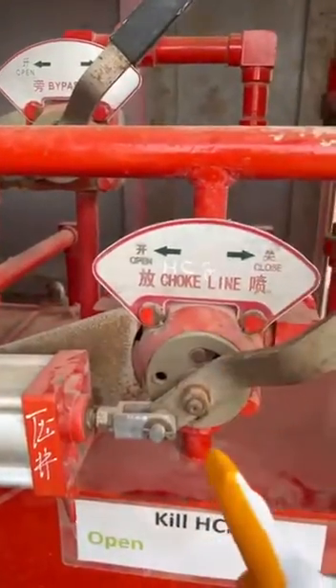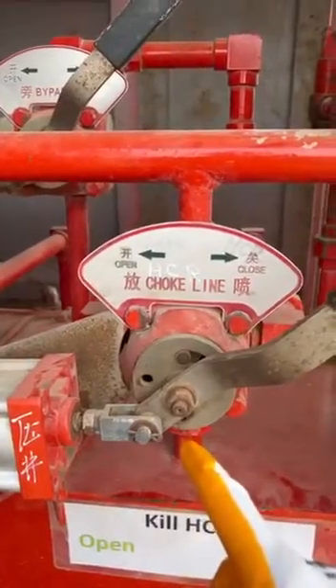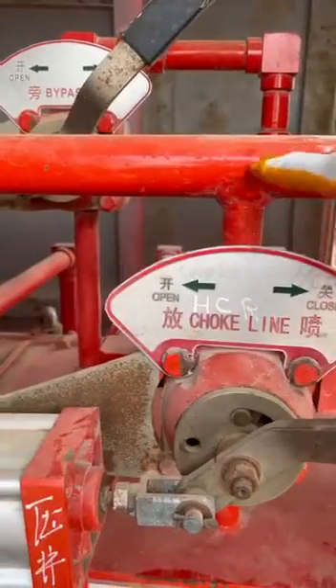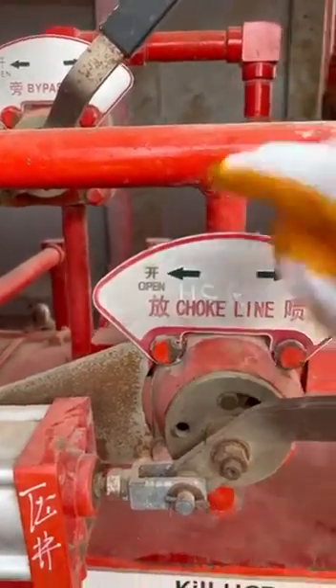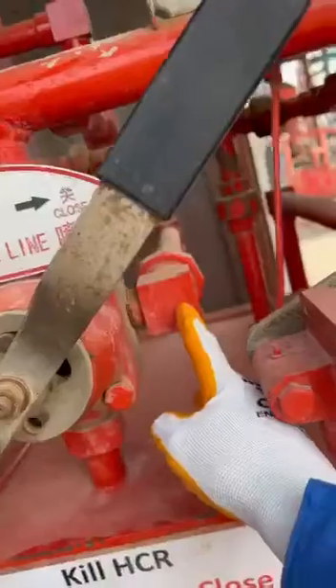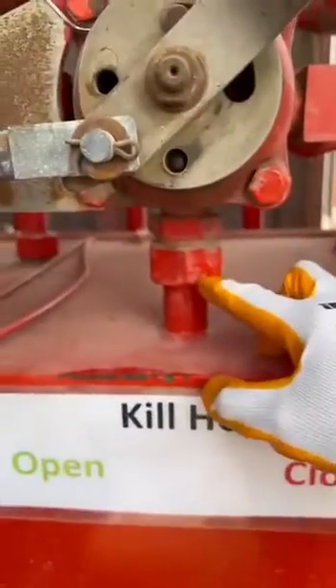Why it's called four-way: because there is one way coming from the manifold — the pressure comes from the manifold to this valve — one way goes to the closing chamber, one way goes to the opening chamber, and one way goes to the hydraulic oil reservoir tank.